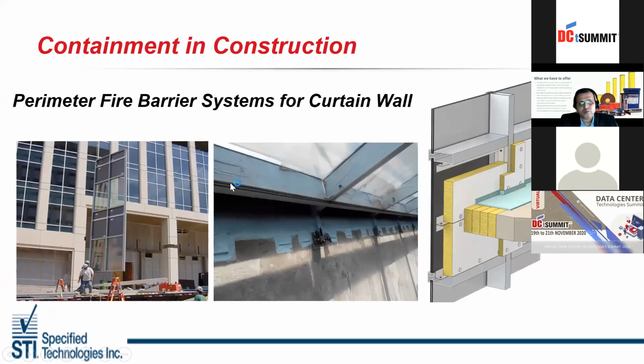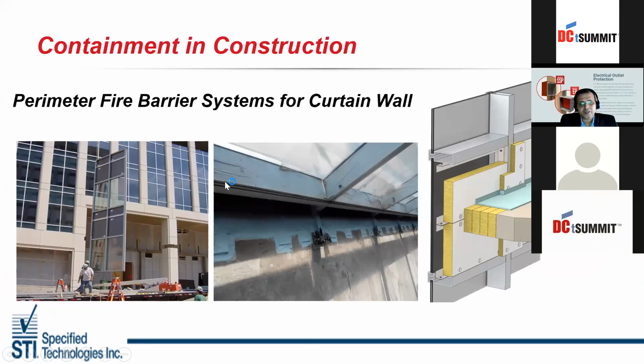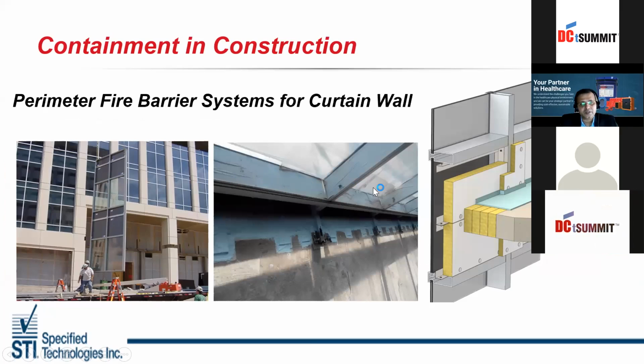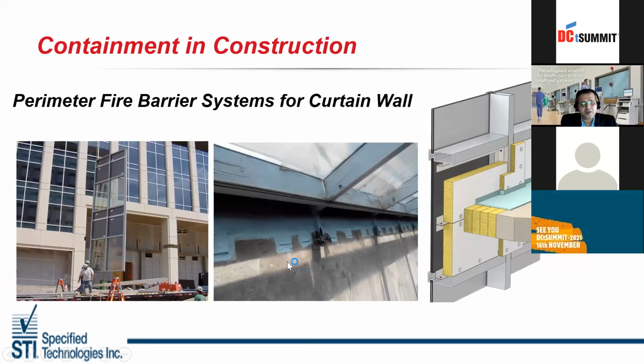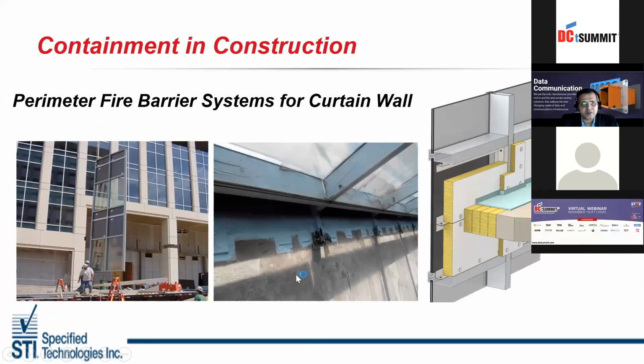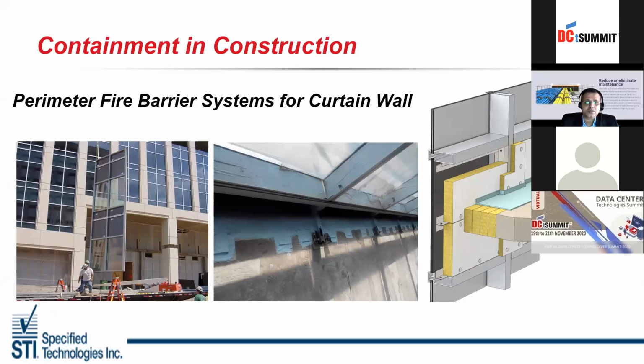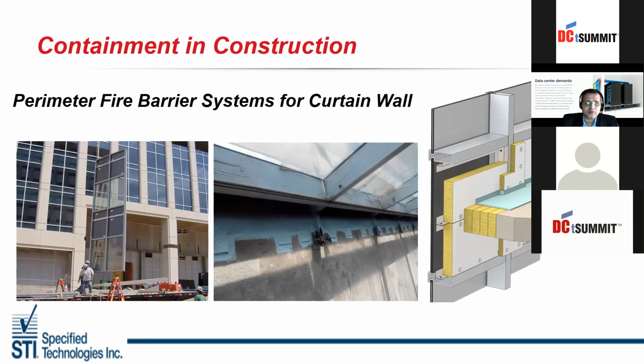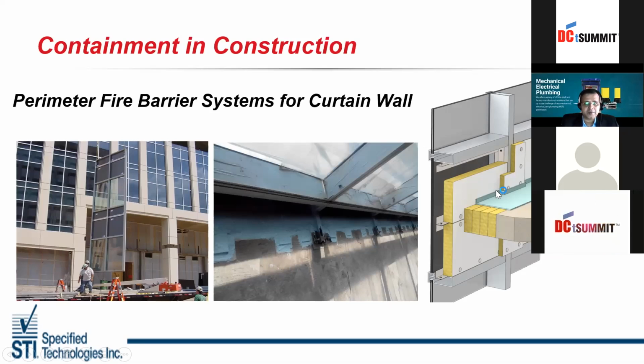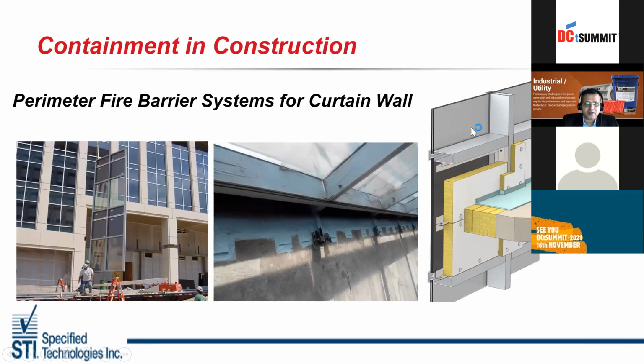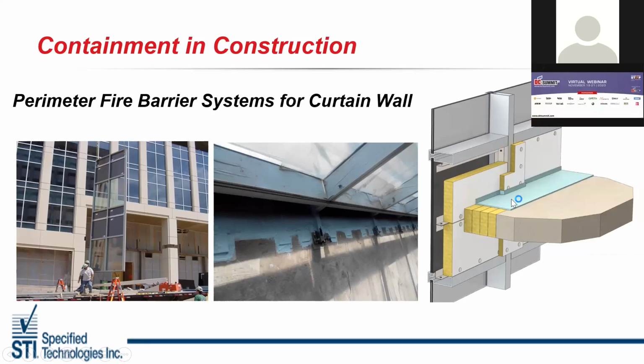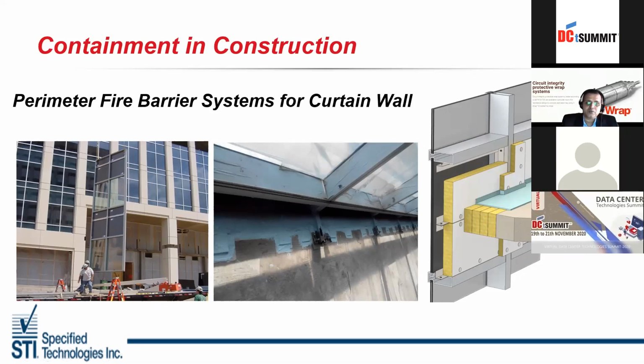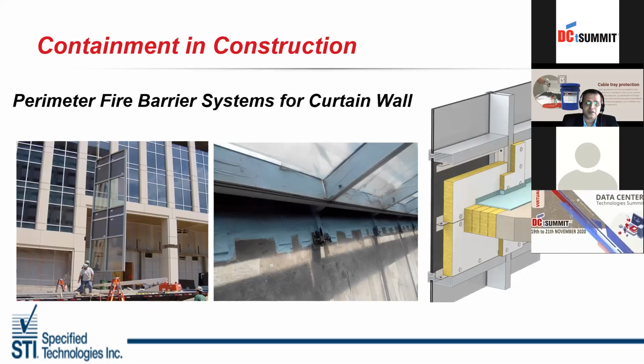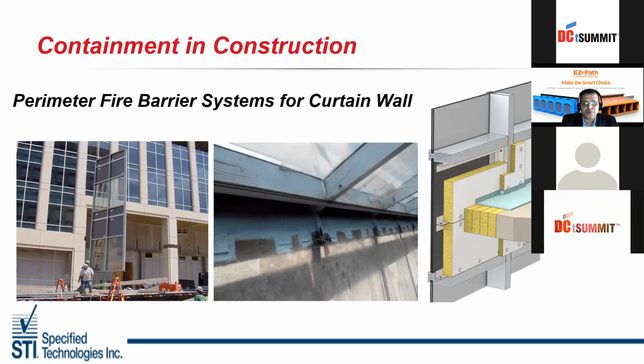Fire barrier, this is what I'm trying to explain here. In the center picture, what you can see is the facade and the floor. The gap there is normally between say 50 mm to 100 mm. Sometimes it goes up to 150 mm. So this area has to be sealed with a fire stopping system. If you see the extreme right-hand side, the floor and the fire facade, there's a gap and there's a pale blue color and the rock wool which has been installed. So this is a complete UL tested system, which can last up to 2, 3 or 4 hours, depending upon the consultants' or the local CFO's approval.